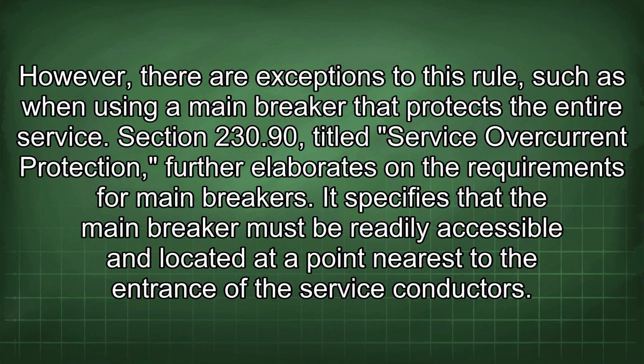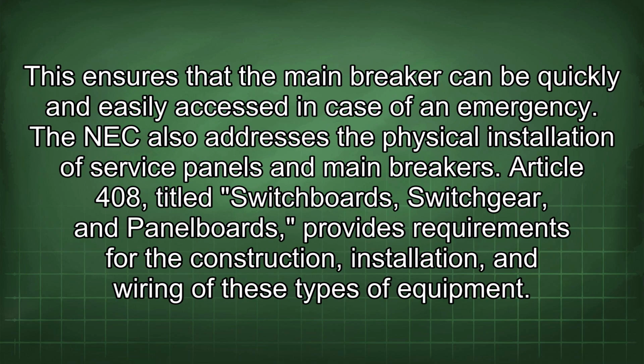Section 230.90, titled Service Overcurrent Protection, further elaborates on the requirements for main breakers. It specifies that the main breaker must be readily accessible and located at a point nearest to the entrance of the service conductors. This ensures that the main breaker can be quickly and easily accessed in case of an emergency.